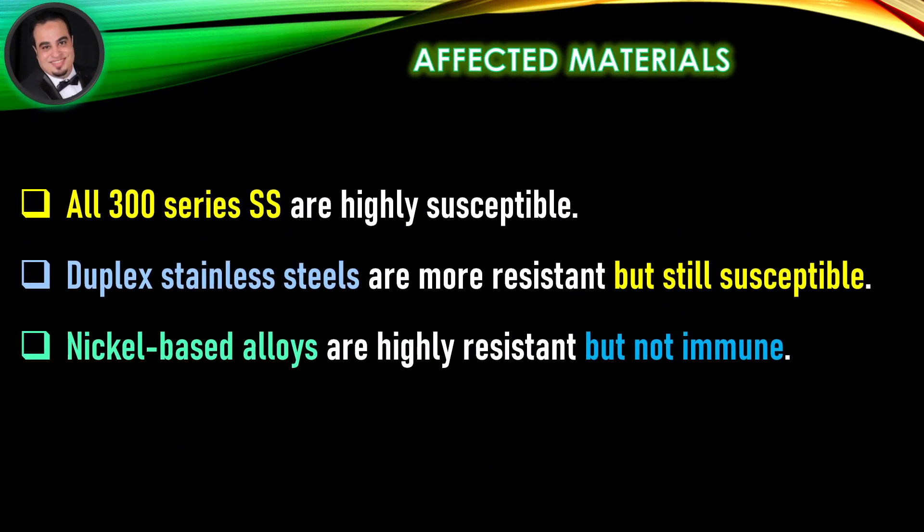Affected materials: All 300 series stainless steels are highly susceptible. Duplex stainless steels are more resistant, but still susceptible. Nickel-based alloys are highly resistant, but not immune.